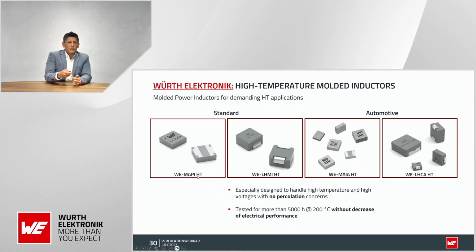If you have an application and you're really concerned, for example I saw a customer with some peaks, going a little higher in terms of saturation, 40%, 50 milliseconds, double the rated current, but that happened almost one time every hour.